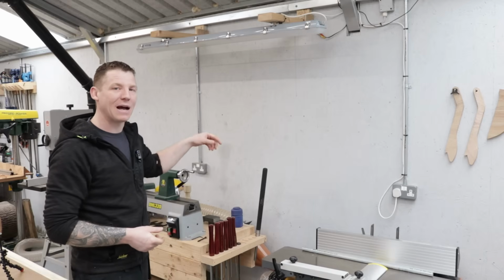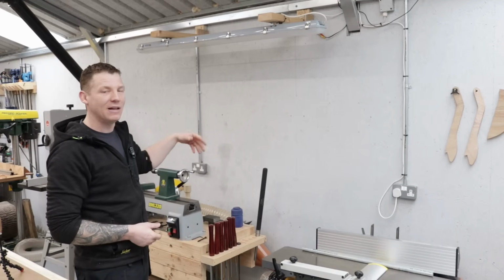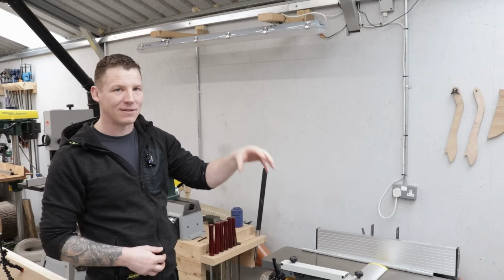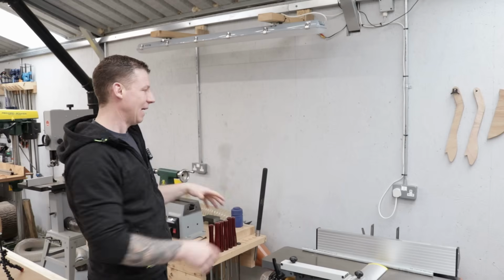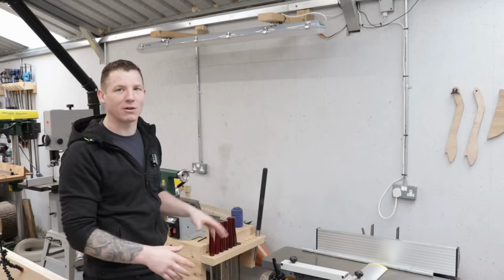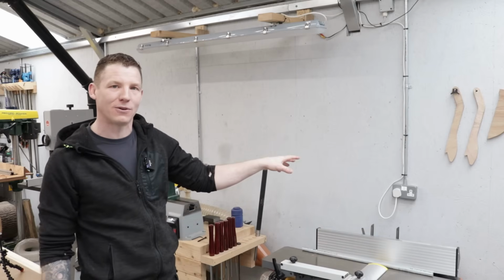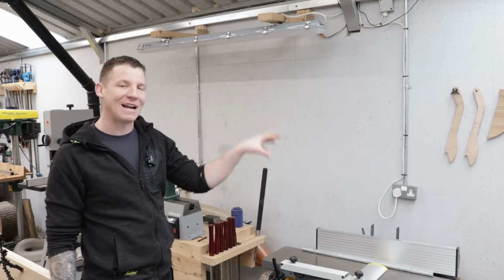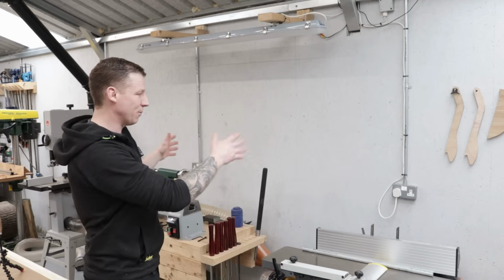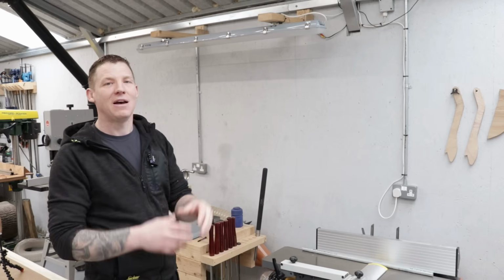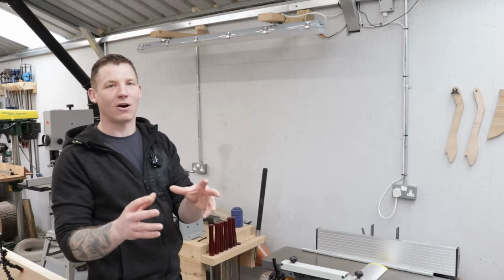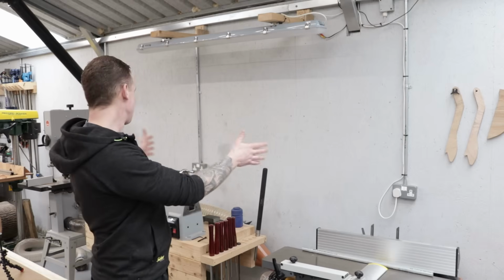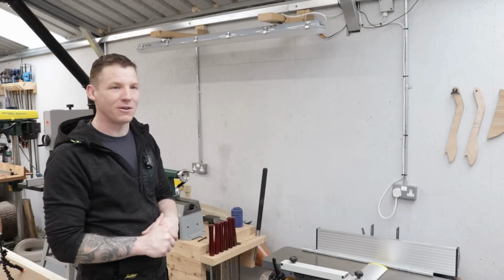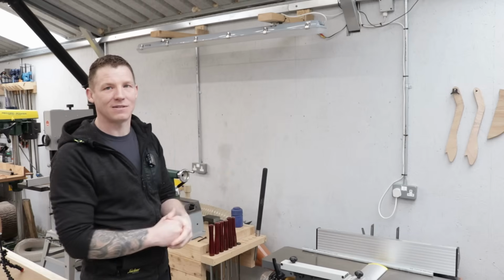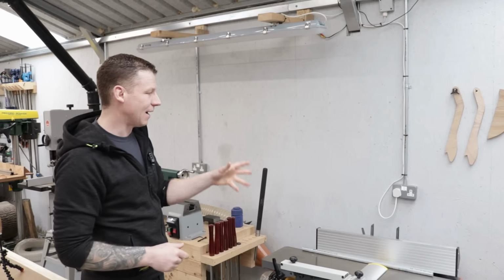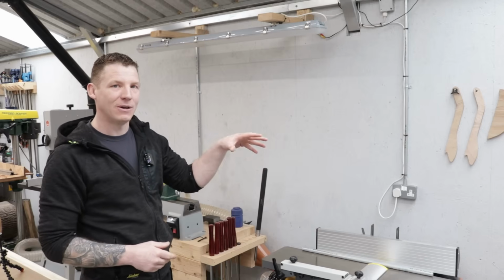So the more sockets we're adding, the longer that circuit is getting, the load it can carry is going down by the time you get to that end socket, and the number of machines that you're going to be plugging in. You don't want to be plugging in 10 machines into one circuit. Some machines might require an individual circuit. So when it comes to your socket circuits, plenty of circuits, not plenty of sockets on a circuit. So keep it maybe 3 or 4 sockets per circuit. That'll allow you to plug in a couple of machines to that socket circuit, and it will also keep the distance of that run down.